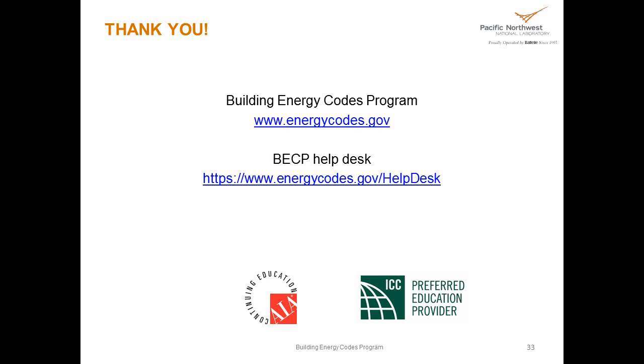The cost of the wiring and the commissioning and installation may still exist, but there are some ways around that too. Nowadays you get wireless sensors, which are more expensive to begin with, but they are much easier to commission. But of course, the trade-off is that wireless means there are more things that can fail, and there are more things that you may have to maintain. So it's a trade-off. But traditional sensors and controllers are coming down in cost. That's just driven by technology, I'm guessing.